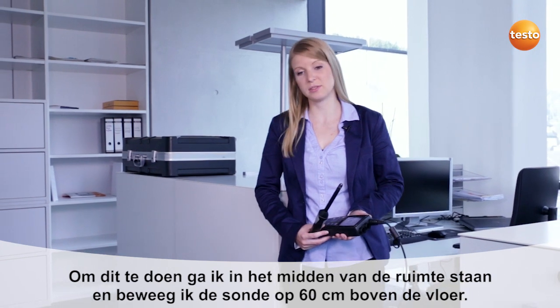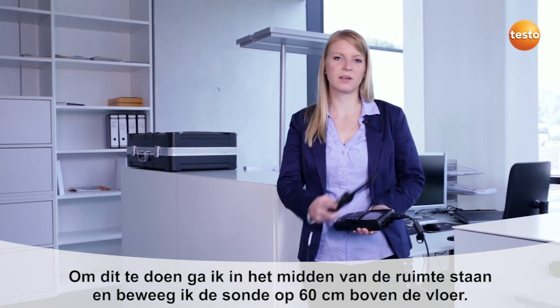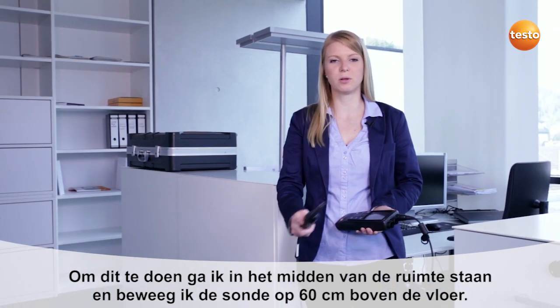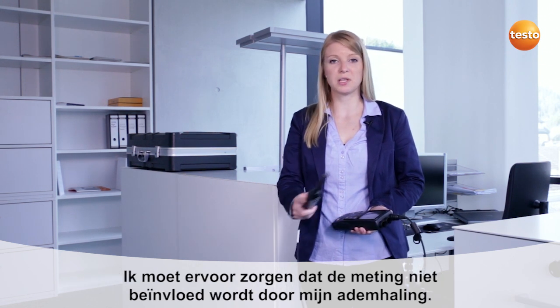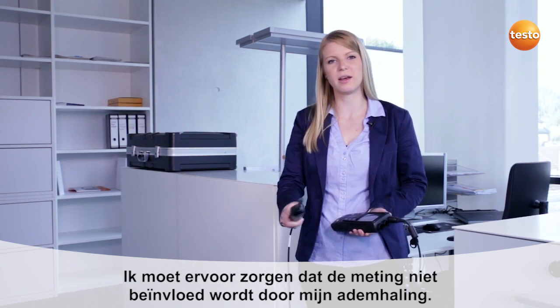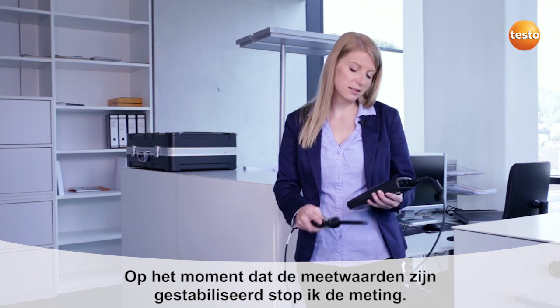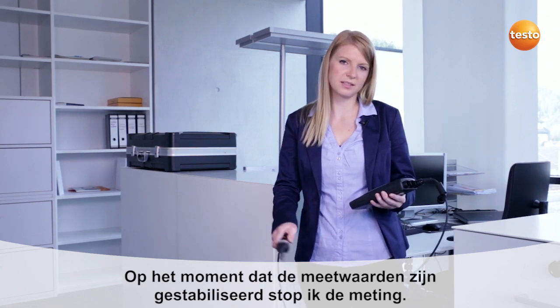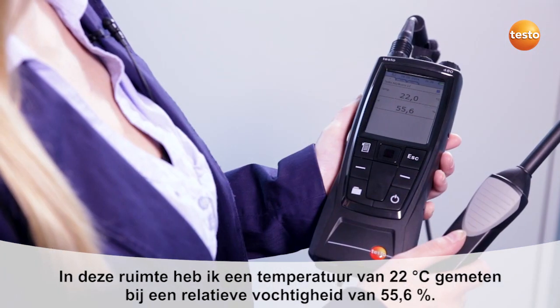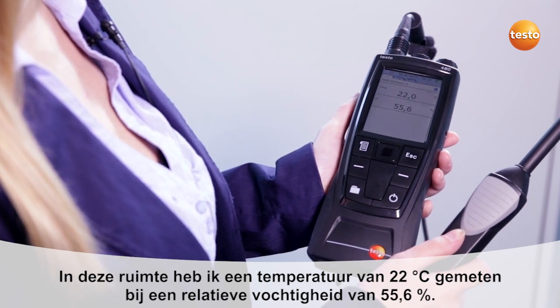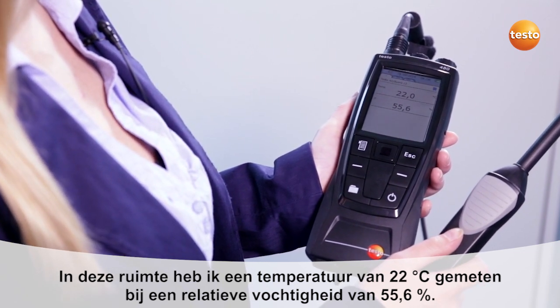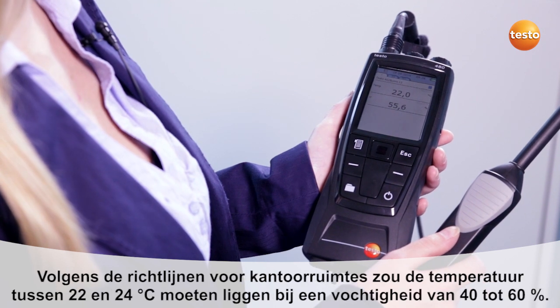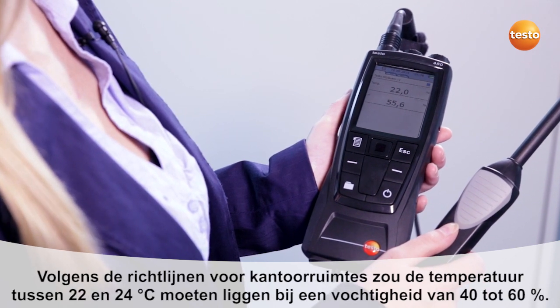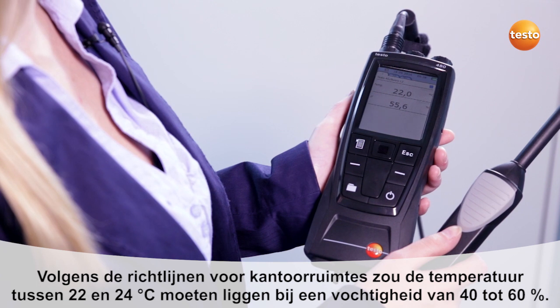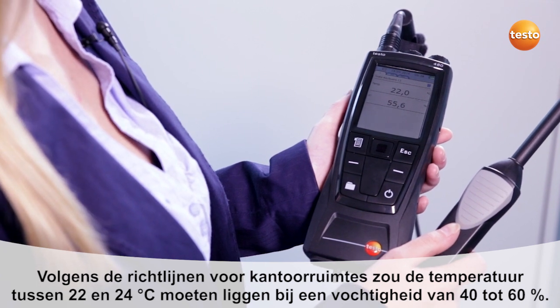To do this, I position myself in the middle of the room and move the probe slightly to and fro, 60 centimeters above the floor. I have to make sure I don't falsify the measurement result with my breath. As soon as the measurement values have stabilized, I can end the measurement. In this office, I've measured a temperature of 22 degrees centigrade and a relative air humidity of 55.6%. The recommended values for offices are between 22 and 24 degrees centigrade and 40 to 60% humidity.